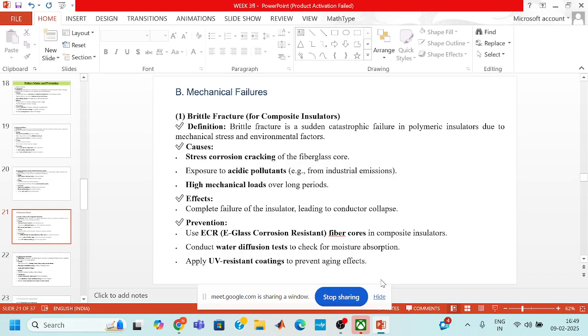So now the next failure is mechanical failures. First is brittle fracture. This is for composite insulators. Brittle fracture is a sudden catastrophic failure in polymer insulators due to mechanical and environmental stresses. It can be caused by stress corrosion cracking of the fiberglass core due to exposure to acidic pollutants, like those from industrial emissions, and high mechanical loads over long periods. Brittle fracture can cause complete failure of the insulators, leading to conductor collapse.